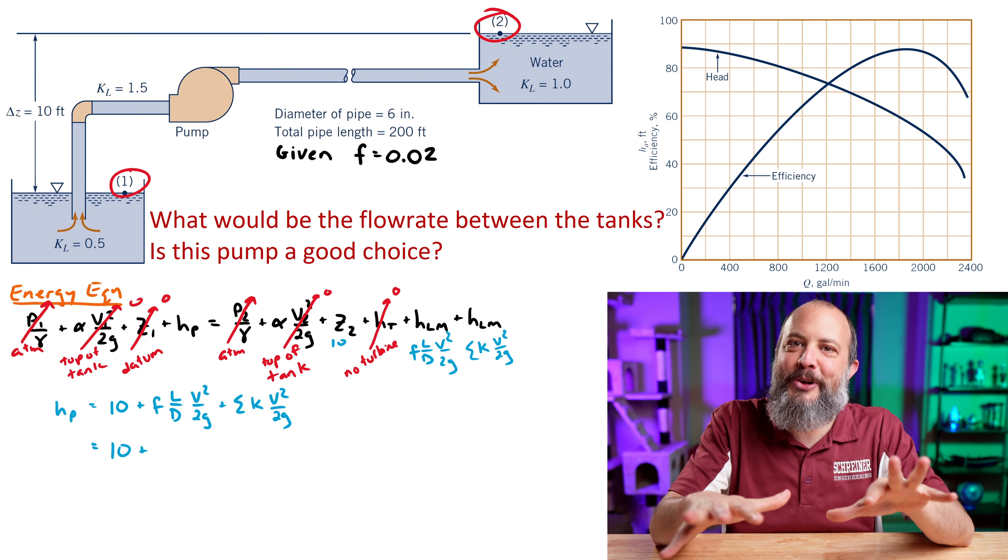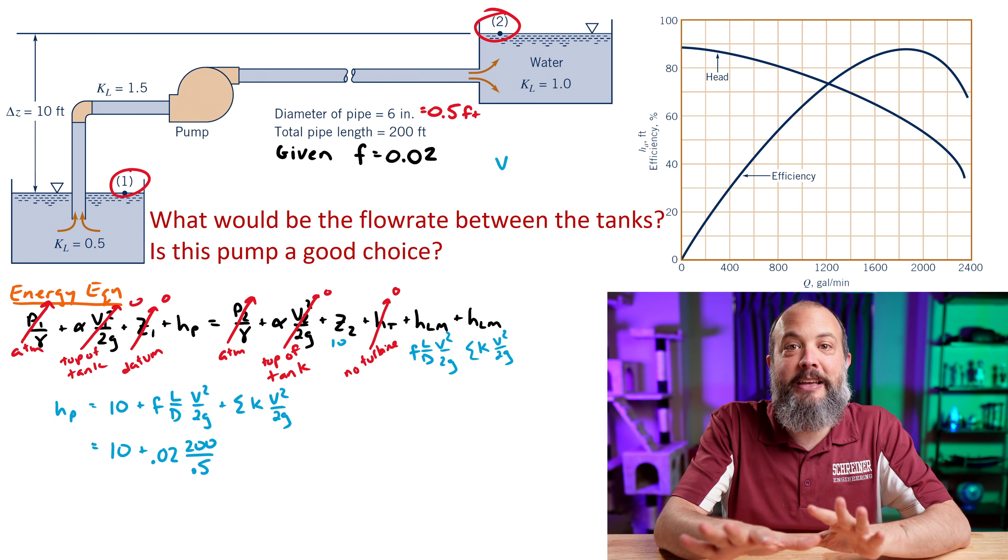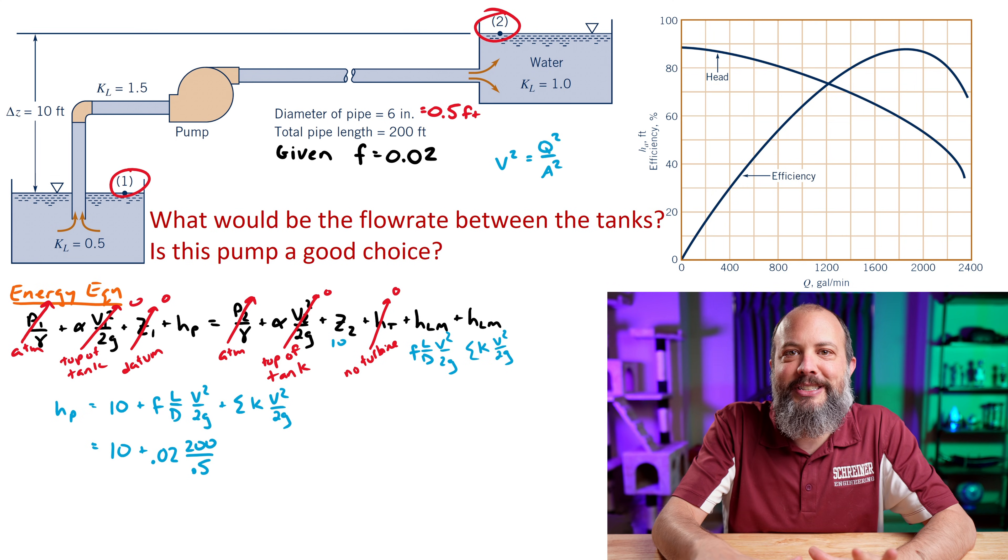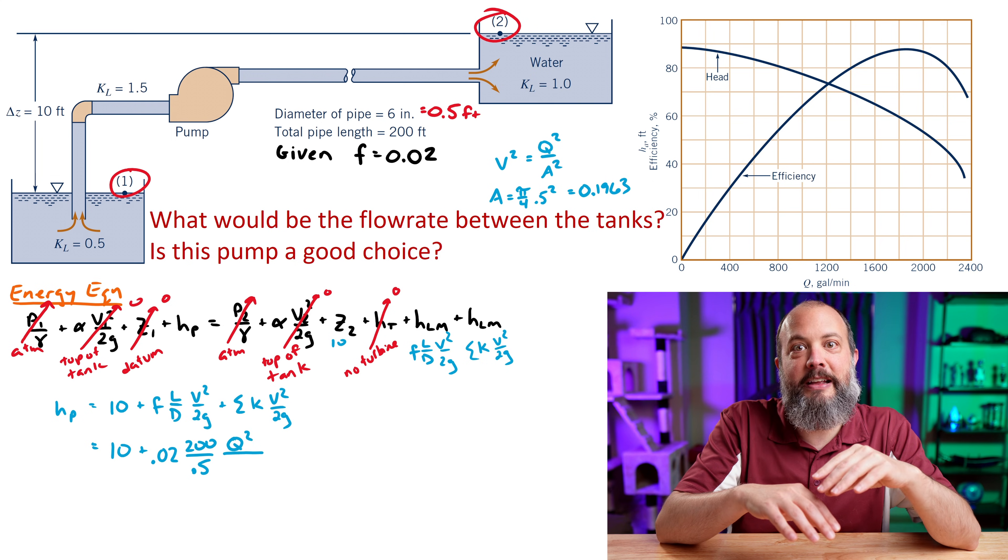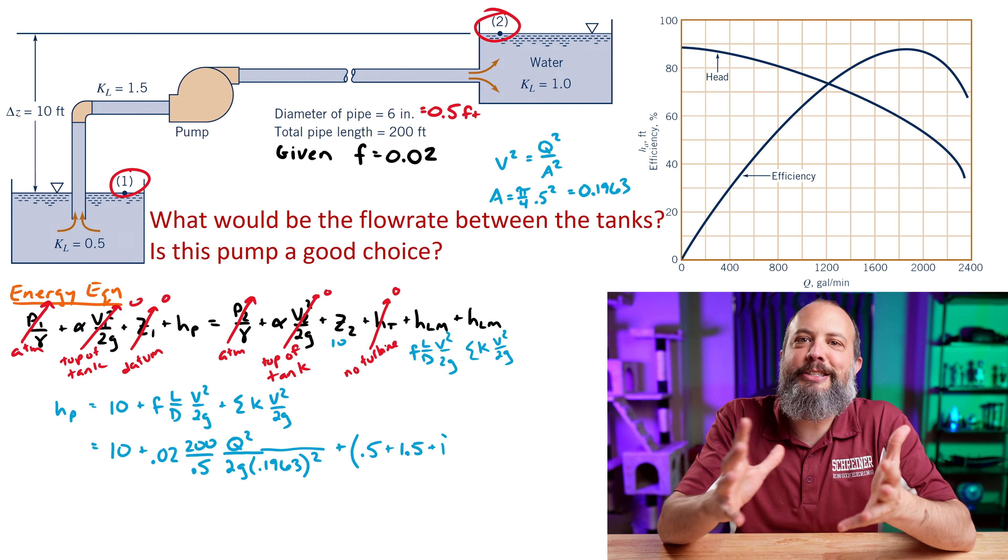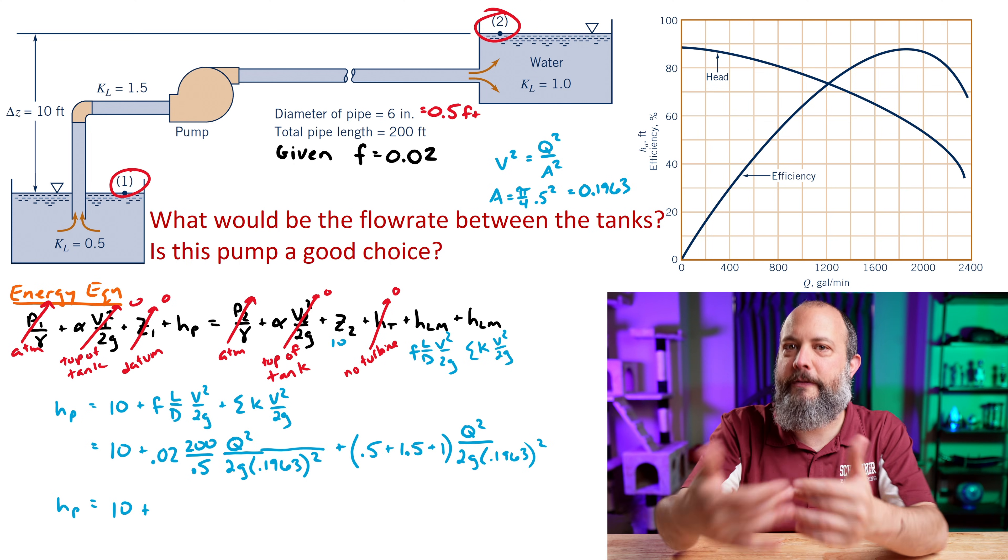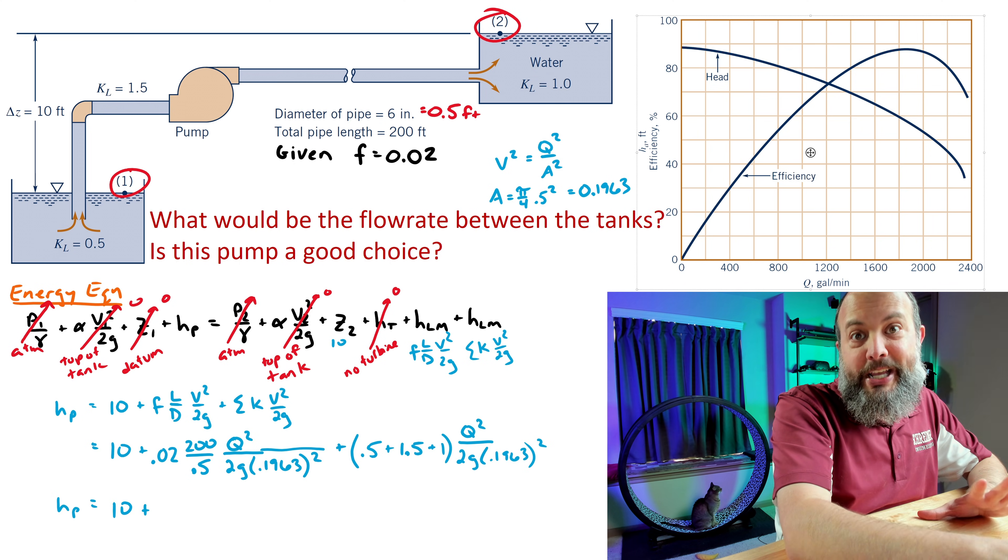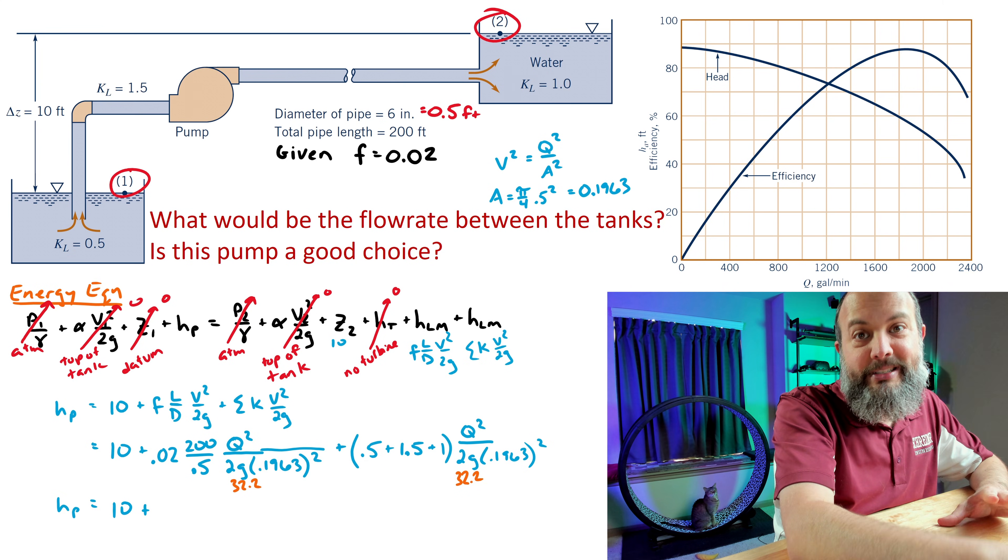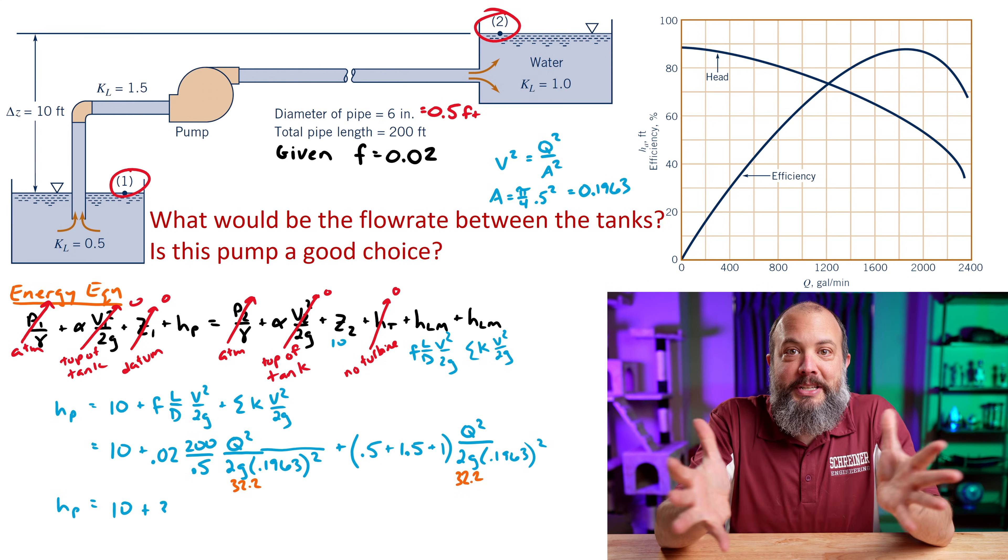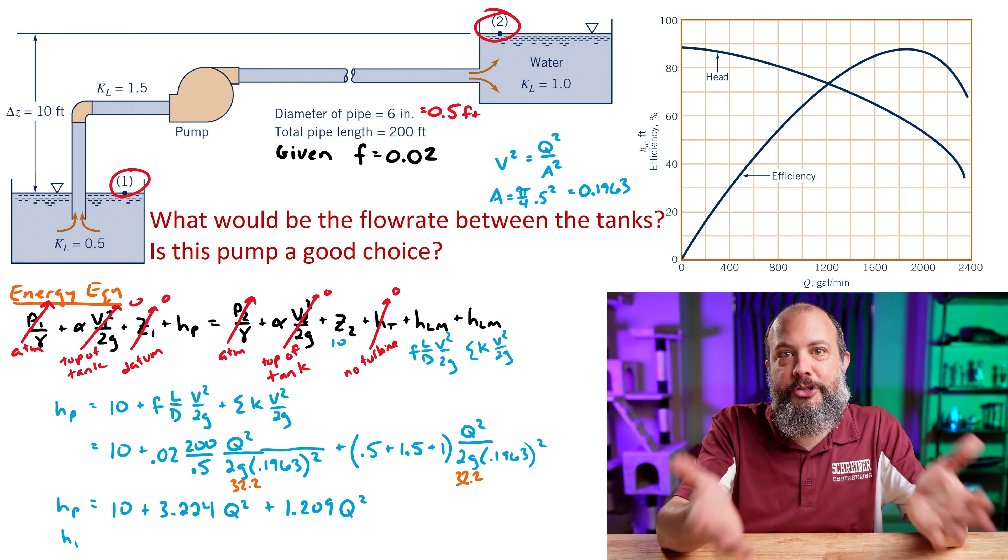And then minor loss is KV squared over 2G. So in this very unrealistic, easier version, you've been given the friction coefficient, 0.02, also given all of the minor loss coefficients. So we just plug those numbers in, and since velocity is Q divided by A, and then velocity squared is Q squared divided by A squared, that's how we're getting flow rate into this equation. We're replacing the velocity terms with flow rate terms. Being super careful to use G of 32.2, since this problem is in English units and not SI units, and this is the system curve. Pump head will be 10 plus 4.4 Q squared.